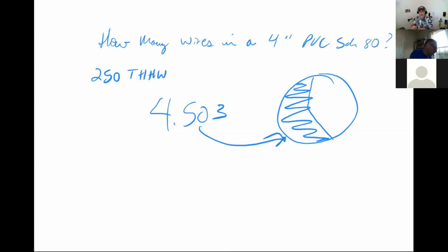So the most important advice I can give you about conduit fill is when you're in table 5, make sure you're on the right row before you start trying to take a value. Make sure you get that insulation identified. THHW at 250 kcmil, I'd be on page 685. I see THHW listed in that group of wire insulation there. So for 250 kcmil, I'm always using the middle column on this table, the one that says approximate area in inches square.